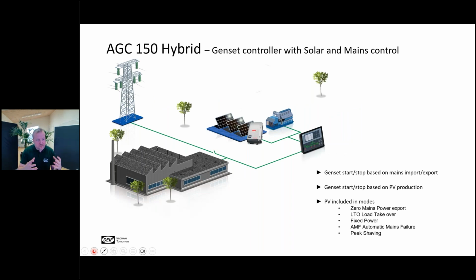And we are also able to connect to a grid connection, just like it's shown here on the picture. So it's more or less the same setup, where one controller is able to control a genset, PV, and also have the mains connection or the grid connection. And we all know that a typical standard Fronius PV system is a current source, so it cannot be the grid forming part. So in this situation, if the grid is the grid forming part, we are able to start and stop the genset, so we further reduce the need for fossil fuels.